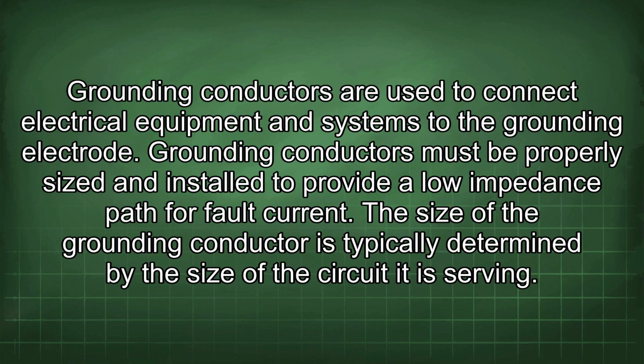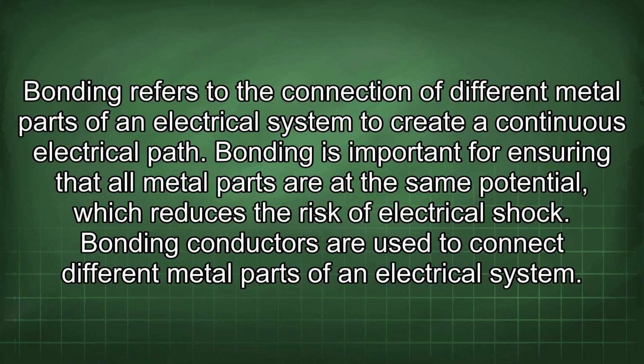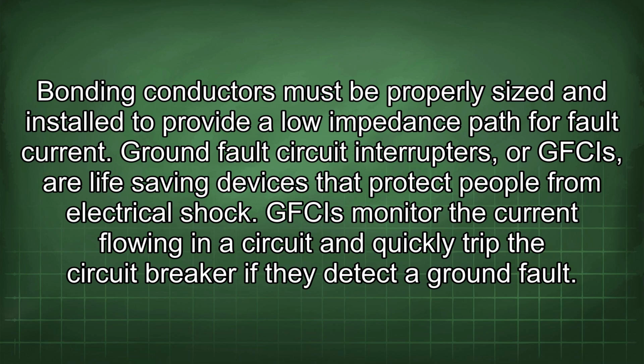Grounding conductors are used to connect electrical equipment and systems to the grounding electrode. Grounding conductors must be properly sized and installed to provide a low impedance path for fault current. The size of the grounding conductor is typically determined by the size of the circuit it is serving. Bonding refers to the connection of different metal parts of an electrical system to create a continuous electrical path. Bonding is important for ensuring that all metal parts are at the same potential, which reduces the risk of electrical shock. Bonding conductors are used to connect different metal parts of an electrical system. Bonding conductors must be properly sized and installed to provide a low impedance path for fault current.